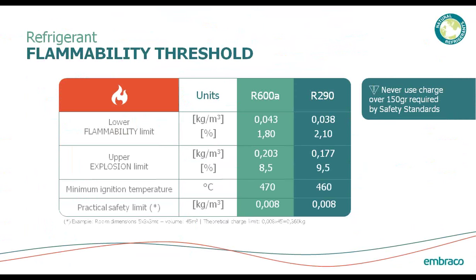When we talk about the flammability of refrigerants, we need to understand what that really means in the practical world. For R600 and R290, there is a lower flammability limit — if the concentration of the refrigerant mixed with air is too low, you cannot ignite it. When the concentration is too high, there's not enough oxygen in the mix and it will not burn. The minimum ignition temperature is around 460–470 degrees Celsius. The practical safety limit tells you how many kilograms in an occupied space are needed for it to be considered safe or not safe.